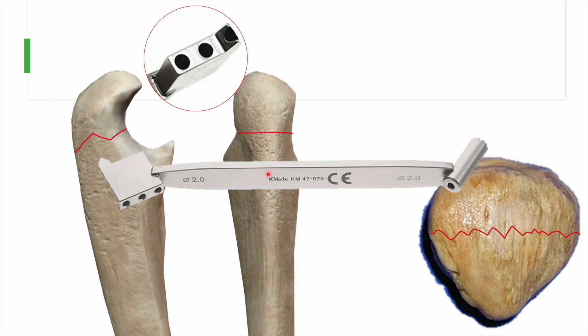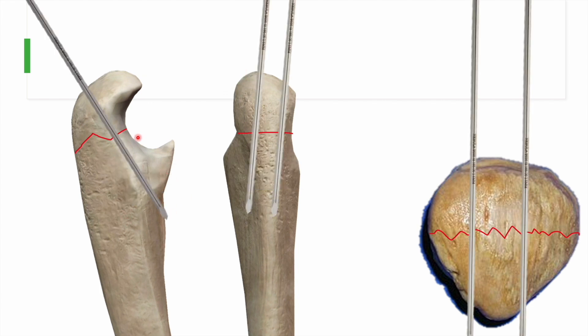The K-wire guide is helpful because it allows multiple K-wires to be placed in parallel. Without the guide sleeve, aligning two wires perfectly can be difficult; with the sleeve that has holes for multiple parallel K-wires, alignment is much easier. The two K-wires should be away from the articular surface but close to the subchondral bone, where they provide maximum stability and prevent rotation and translation at the fracture site.